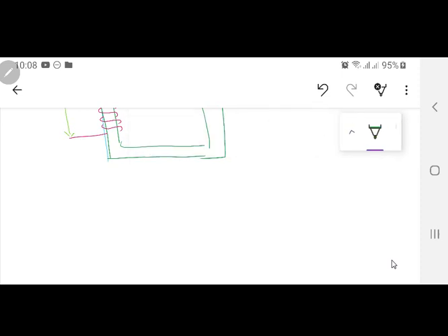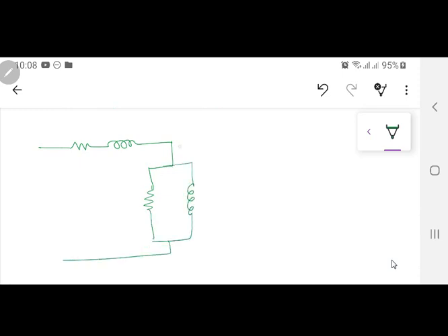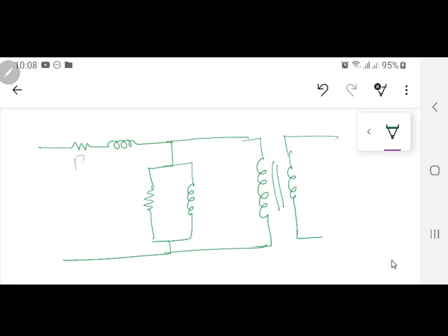If I'm drawing the equivalent circuit of a transformer, this was the equivalent circuit, and this one was the primary winding, and then there was the core. And then this was the ideal transformer over here, and certainly you can draw the secondary. I'm not concerned with the secondary. Now this is RP and this is jXP. Now the inter-turn capacitance is going to be either parallel to this RP and jXP, or in series, but we don't want this series capacitance.